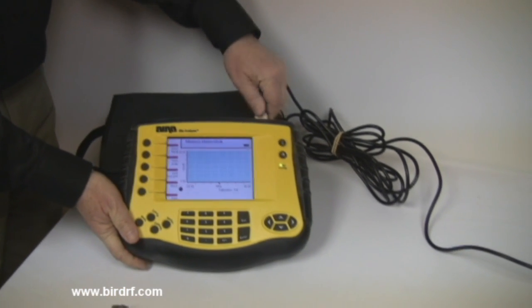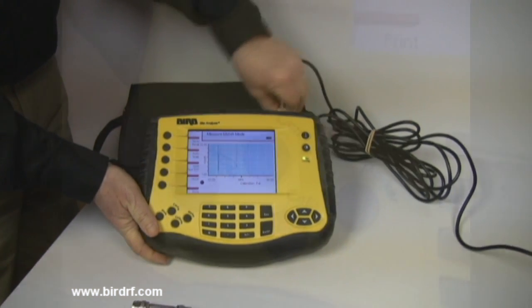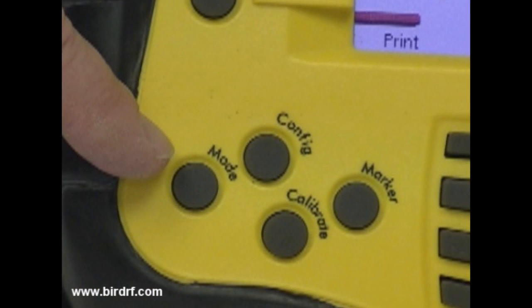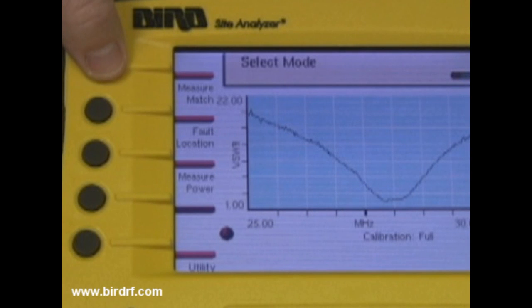Step one of the measurement procedure is to take the antenna connection cable and attach it to the test port. Next you will need to press the mode button located in the bottom left hand corner of the Site Analyzer. This brings up a select a mode option on the screen.